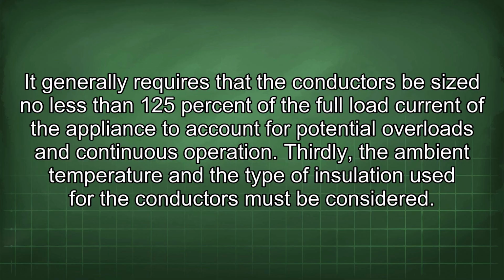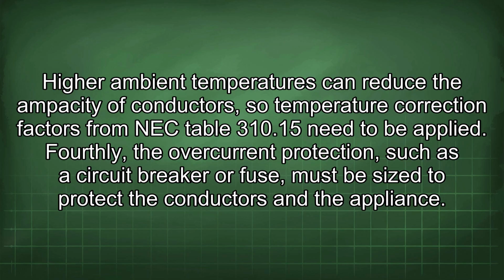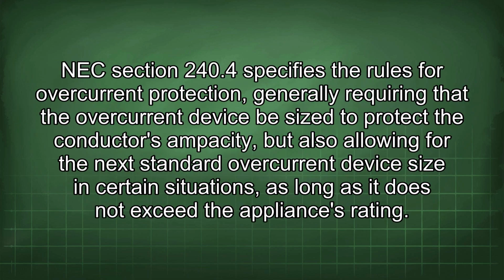Thirdly, the ambient temperature and the type of insulation used for the conductors must be considered. Higher ambient temperatures can reduce the ampacity of conductors, so temperature correction factors from NEC Table 310.15 need to be applied. Fourthly, the overcurrent protection, such as a circuit breaker or fuse, must be sized to protect the conductors and the appliance. NEC Section 240.4 specifies the rules for overcurrent protection, generally requiring that the overcurrent device be sized to protect the conductor's ampacity, but also allowing for the next standard overcurrent device size in certain situations, as long as it does not exceed the appliance's rating.